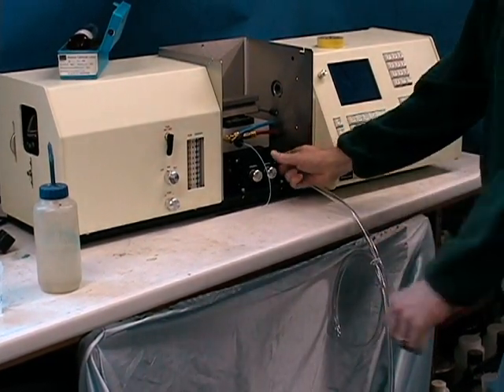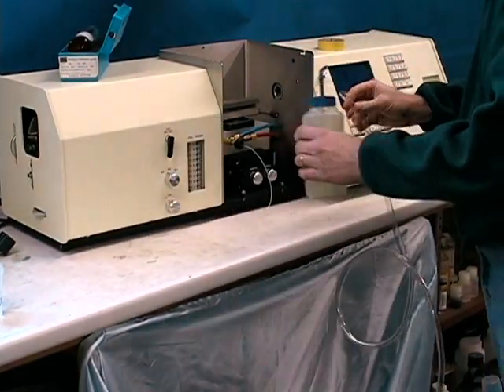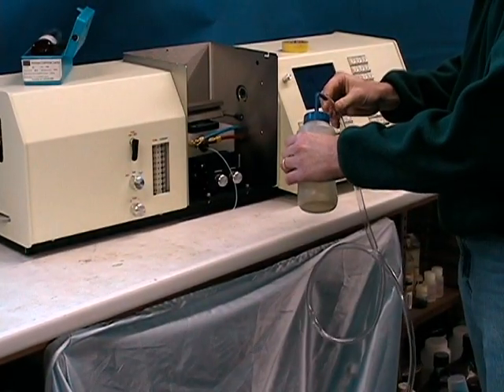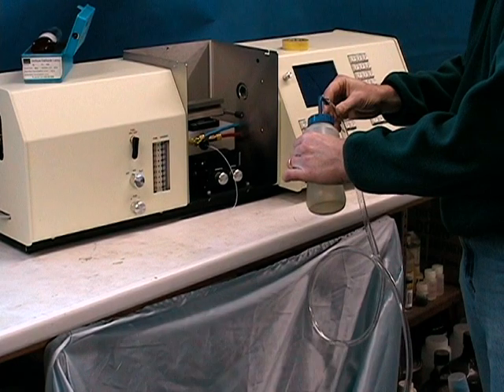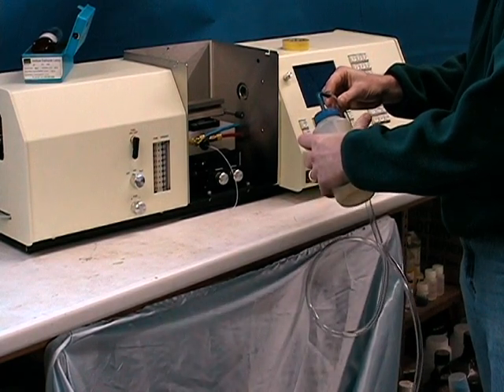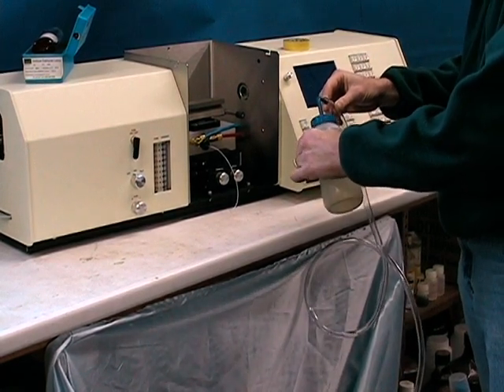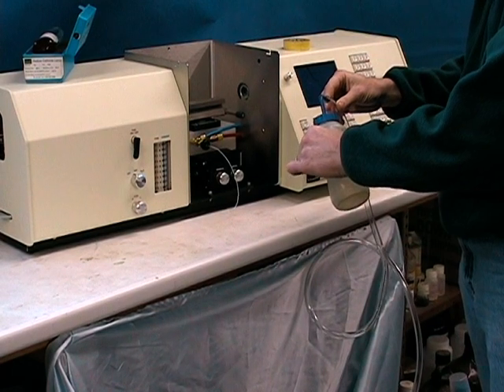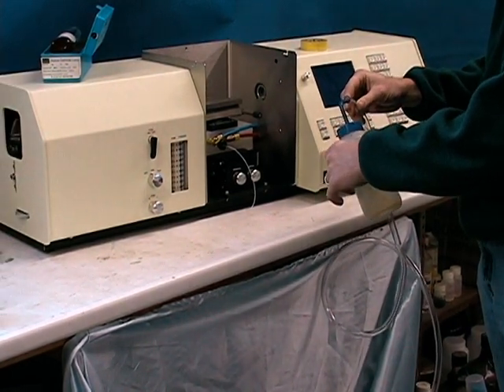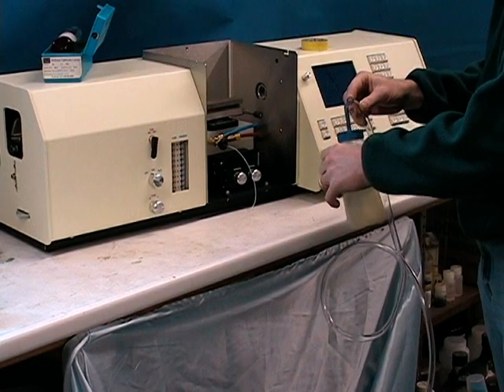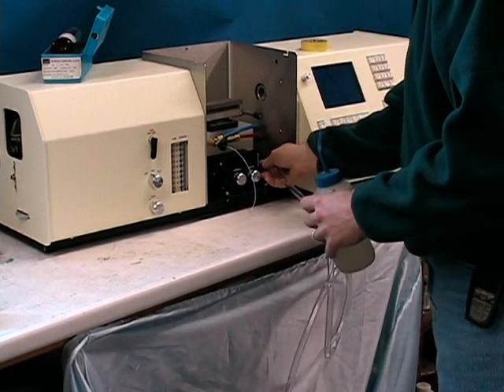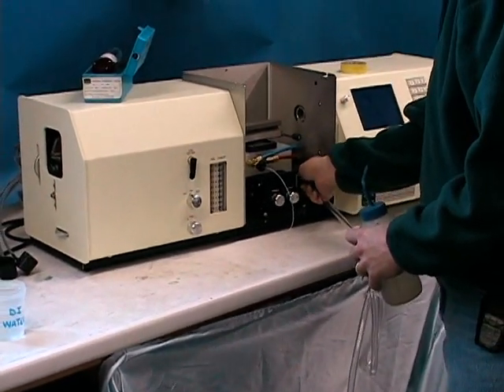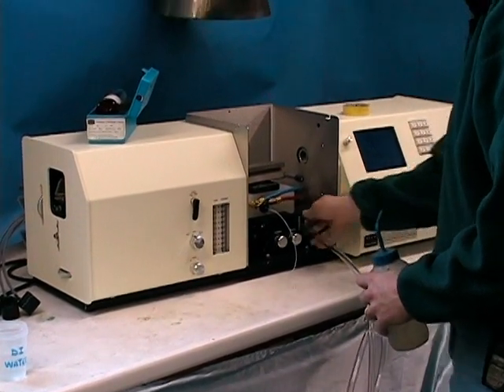Then using a squirt bottle of water, remove the end of the line from the nipple and proceed to fill it. This will prevent the flammable acetylene gas from leaking into your waste container and causing a possible flashback. Once the loop is full, reattach it to the nipple on the burner head, and this will require very little future maintenance.